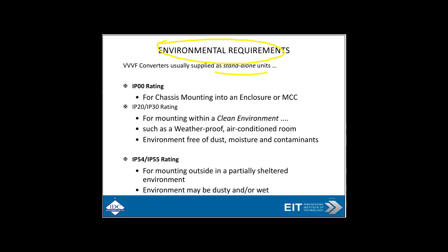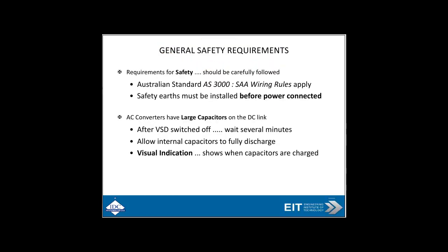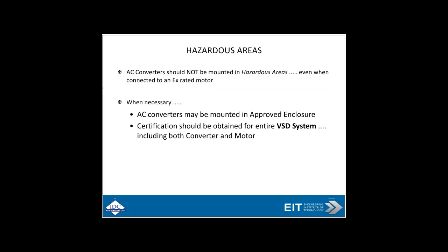Obviously supply and stand-alone units come in various IP ratings, and requirements of safety need to be carefully followed — such as the wiring rules, whether it's the Australian wiring rules, the NEC (National Electrical Code) in the States, or the wiring rules in the UK. These need to be followed. AC drives have large capacitors, so there's a potential problem with discharge of capacitors — just be wary of those issues. For hazardous areas, you can't just plug a variable speed drive in; it needs to be in approved enclosures.